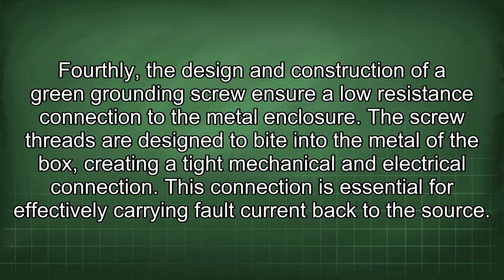Fourthly, the design and construction of a green grounding screw ensure a low resistance connection to the metal enclosure. The screw threads are designed to bite into the metal of the box, creating a tight mechanical and electrical connection. This connection is essential for effectively carrying fault current back to the source.